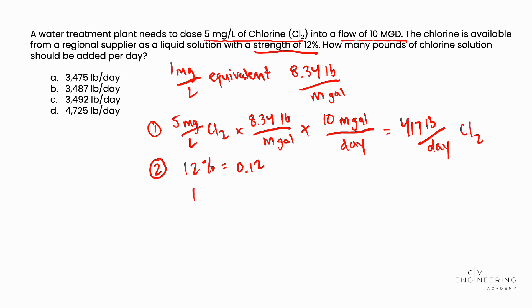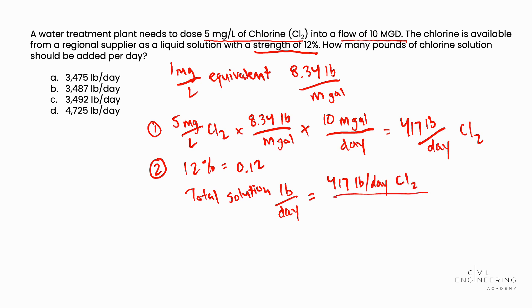So we'll take our total solution in pounds per day. That is going to be equal to: we said we needed 417 pounds per day of chlorine, and we'll divide that by the strength of the chlorine in the solution, which we're told is 12% — 0.12 in decimal form. We work this calculation out and determine that for our total solution in pounds per day, we need 3,475 pounds per day of the solution.